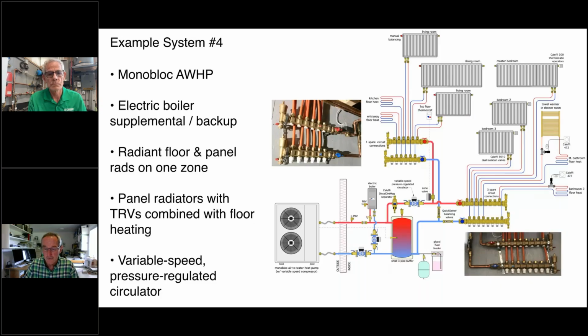We've got a zone valve that controls flow to a manifold. That manifold serves a combination of some floor circuits as well as some panel rads. Notice there's no TRV on these panel rads. Okay, so basically a thermostat opens this, turns on the circulator, and this is all controlled as a single zone. This is all one big open area. Over here, we do have thermostatic radiator valves on this. We've got a towel warmer with a capillary tube TRV. We've got another floor circuit with a TRV on it. And so these are all independently controlled non-electric zoning.